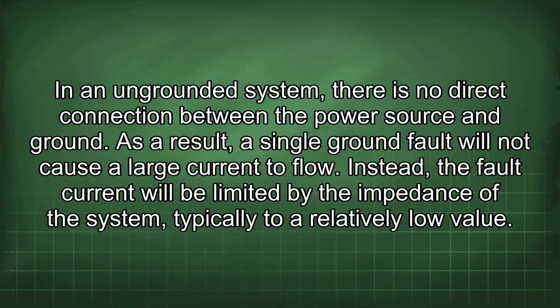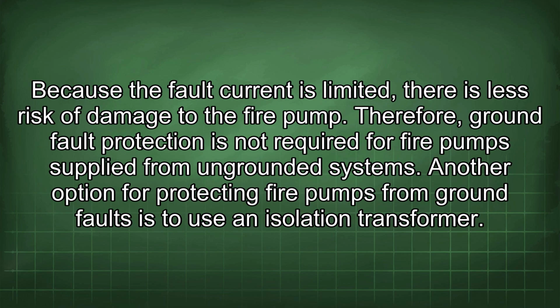As a result, a single ground fault will not cause a large current to flow. Instead, the fault current will be limited by the impedance of the system, typically to a relatively low value. Because the fault current is limited, there is less risk of damage to the fire pump. Therefore, ground fault protection is not required for fire pumps supplied from ungrounded systems.